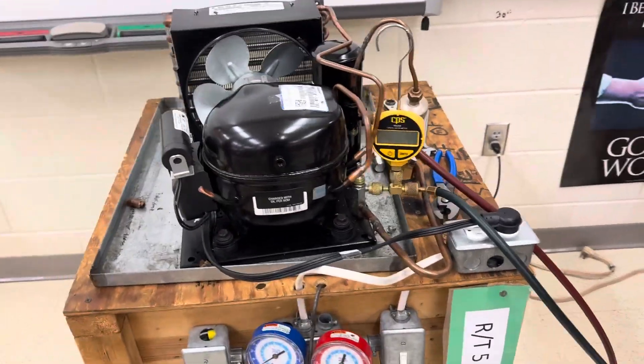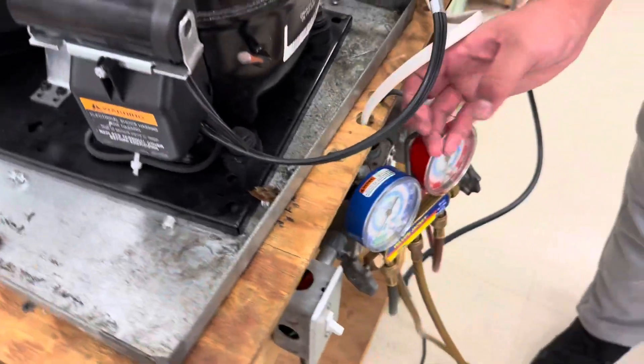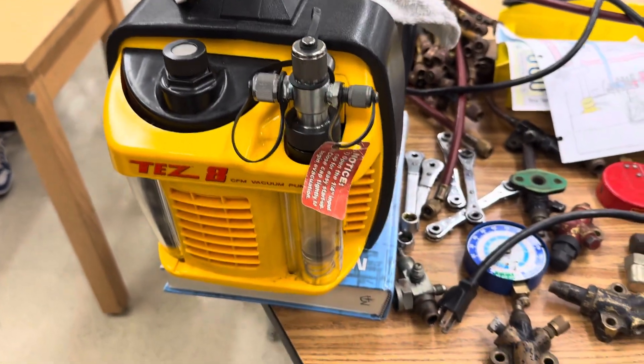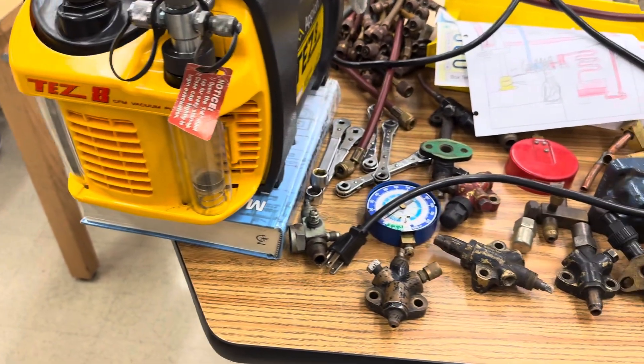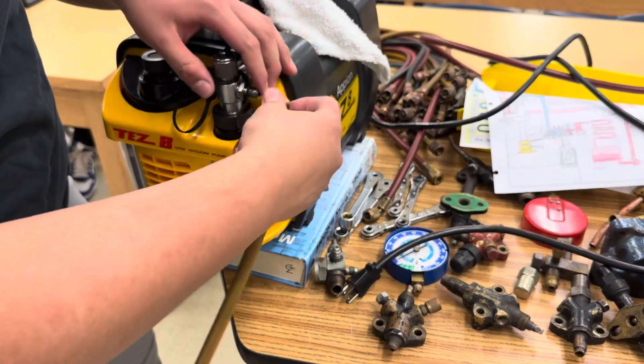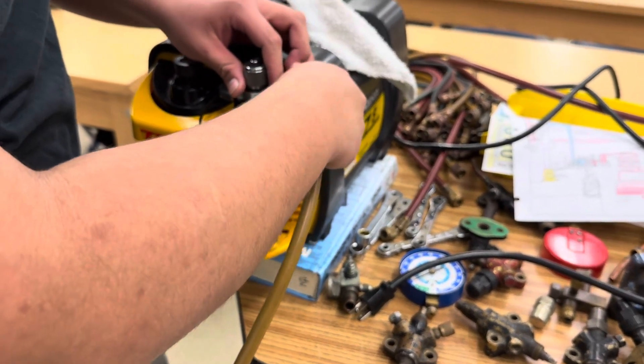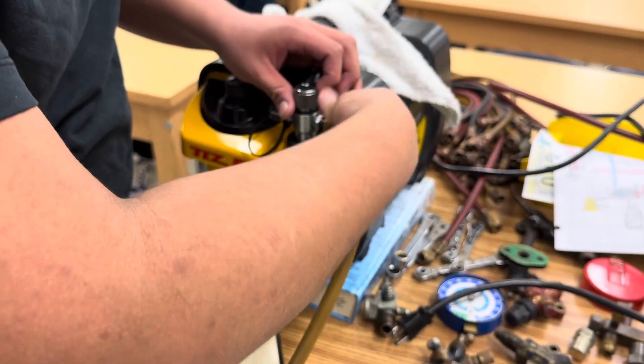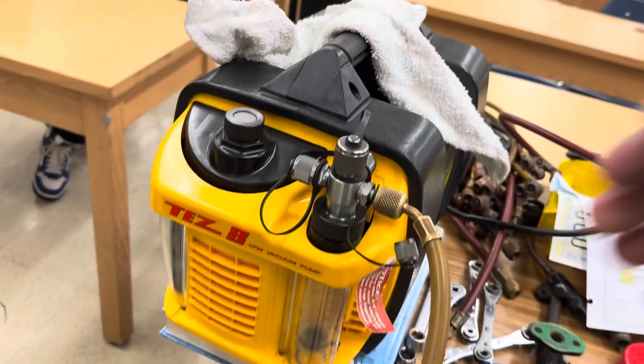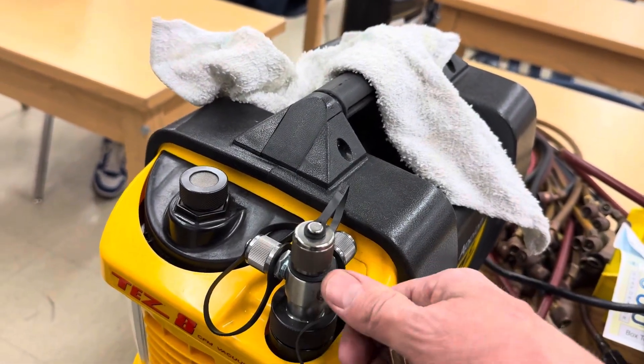Now we're going to go ahead and hook the yellow hose. That center hose is for all accessories, and our accessory today is going to be the TEZ-8 vacuum pump, so you're going to hook to that quarter-inch connection right there. Sometimes there's a gas ballast that allows us to start the unit off with a little bit of a vapor opening to balance the pressure — this one does not require that — but we will leave it a little loose to start, and then once it gets going we'll tighten it up.